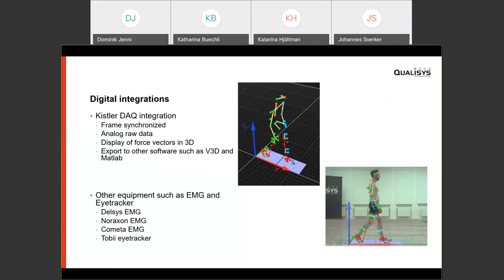The Kistler integration is digital, using the Kistler DAQ box. All data is frame-synchronized and the analog raw data is available in QTM. Forces can be displayed in 3D and exported to software such as Visual3D and MATLAB. It's also possible to use other equipment with the Qualisys system such as EMG and eye trackers — a list of supported devices is available.